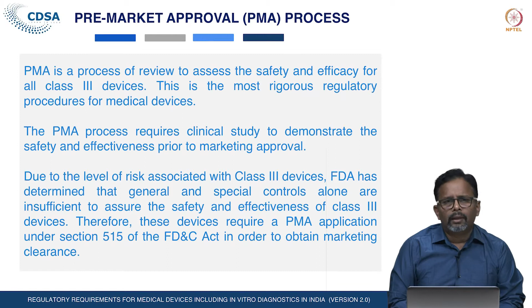Due to the high level of risk associated with class 3 devices, FDA has determined that the general as well as the special controls alone are insufficient to assure the safety and efficacy of the devices. Therefore, these devices require PMA applications under section 515 of the Food, Drug and Cosmetic Act in order to obtain the marketing clearance. PMA is the most stringent type of device marketing application required by the FDA, and the applicant must receive the approval from the FDA prior to marketing of the devices in the US market.